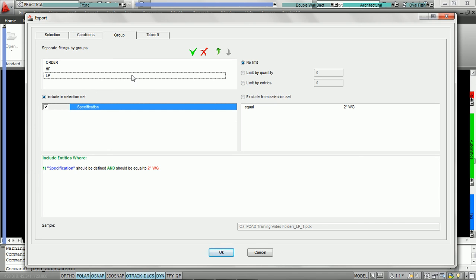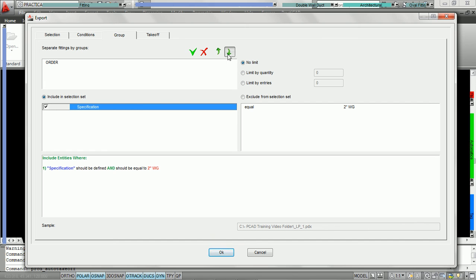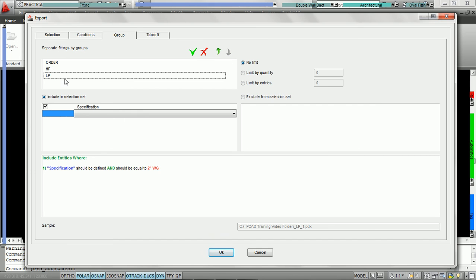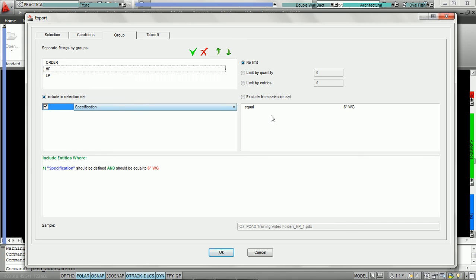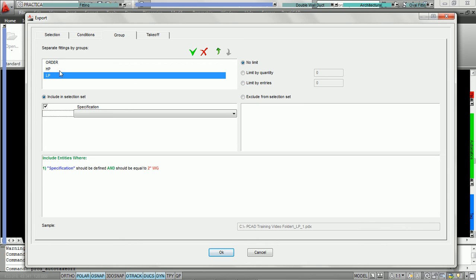You will notice when you add more to this list, Practicad will open up the delete icon plus the up and down arrows. For example, if we have LP selected and hit up, it's going to move it up in order, and down moves it down in order. Order of conditions is important, and under the tutorials for the Practicad layer mechanism, we show and explain why you want to order things properly. Practicad, when it goes to decide what should go in what group, is always going to start with the first choice, see if the conditions meet the selection criteria, and if it does, it's going to put it under order. If it doesn't meet those conditions, it jumps to the next and says: does my specification equal 6 inch water gauge? If yes, it goes in the group high pressure. If it doesn't meet those conditions, it'll jump to the next one and so on. Please watch the tutorials on how to design the Practicad layer mechanism and ordering.